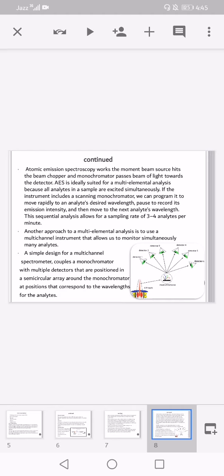Atomic emission spectroscopy works when the beam source hits the beam chopper and monochromator, passing a beam of light towards the detector. Atomic emission spectroscopy is ideally suited for multi-elemental analysis because all analytes in a sample are excited simultaneously. If the instrument includes a scanning monochromator, we can program it to move rapidly to the analyte's desired wavelength, pause to record its emission intensity, and then move to the next analyte's wavelength.